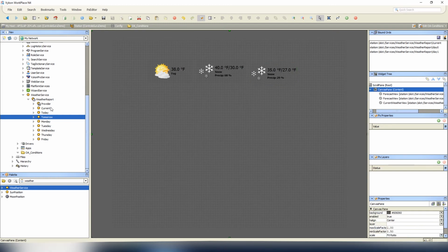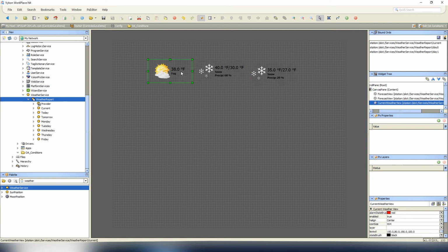Second thing that I like to do, most importantly for the system, is I like to take the weather report and use the temperature and or humidity as the setback or lowest priority OA global outdoor air temp. And that way, if for some reason you lose your outdoor air sensors on the building, it could resort to using the global outside air temp sent from the National Weather Service.